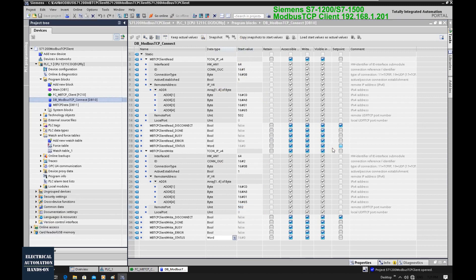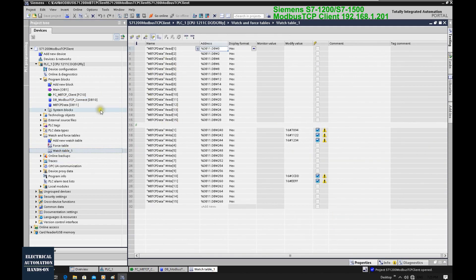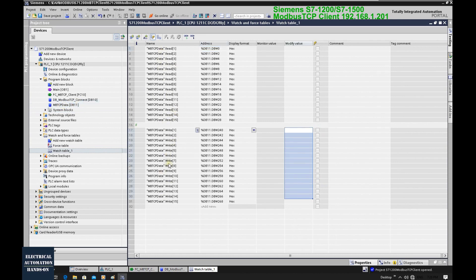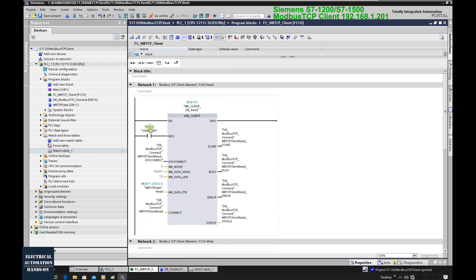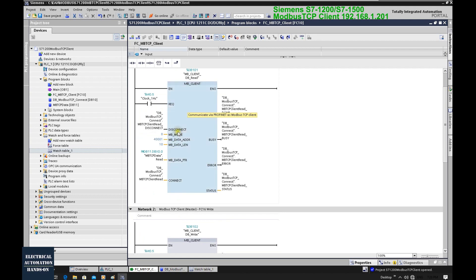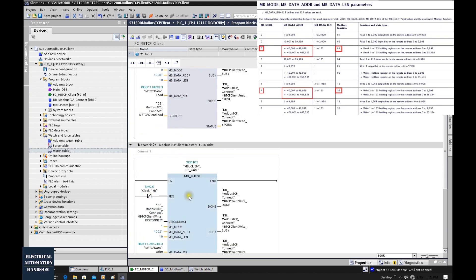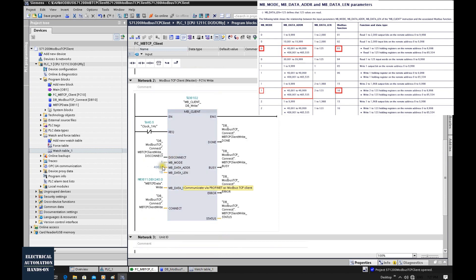To test data communication, we can set up a watch table. In this watch table, I will drag in the Modbus TCP read and write buffer data to monitor and set values. To alternate between the two function blocks, I'm using M0.5, which is a 1 Hz clock. When it's on, it triggers the read; when it's off, it triggers the write function block. The write starts from Modbus address 40,021 with a length of 10.